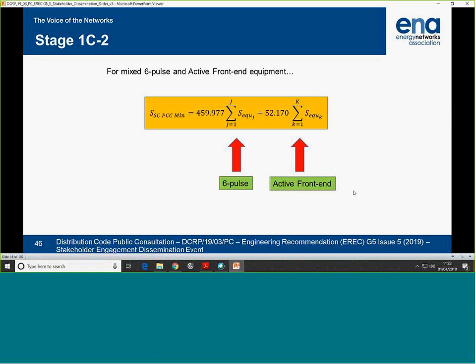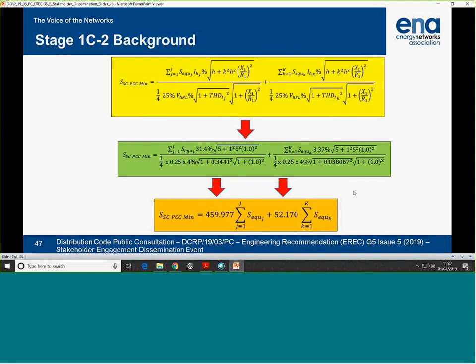The value for the 6 pulse is much higher than the value for the active front end. I quoted these values a moment ago, 460 and 52. The formula, again, is written up in the background. Look at it in detail if you want. What you can see here is the 6 pulse has this distortion, 31.4%. The active front end is much cleaner, 3.37.